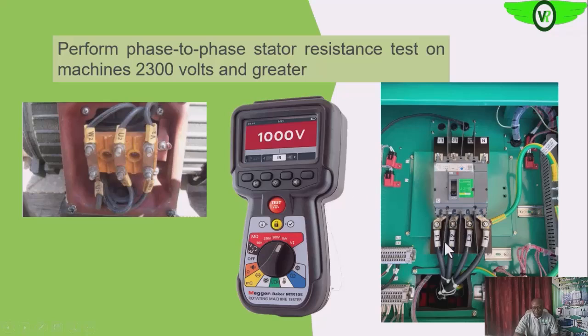Then for generators, remember it has been starred. So the star point is this neutral. You can measure between the neutral and line 1, which will give you the resistance of the first phase; line 2, second phase; line 3, third phase. All of those will give you the resistances of each of those windings. It is very important that you measure these resistances, because a little discrepancy in those resistances can cause imbalance in those high voltage equipment.